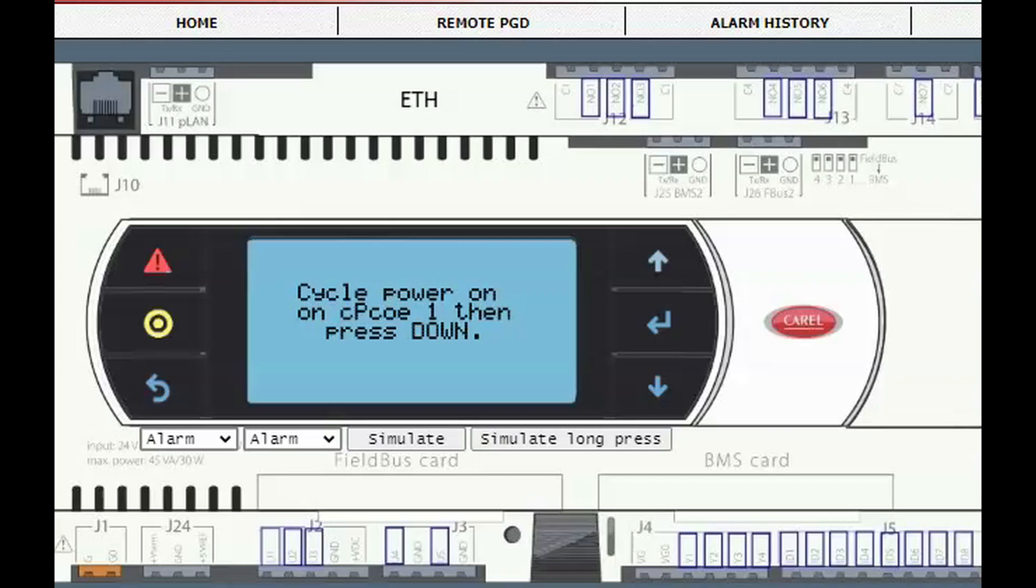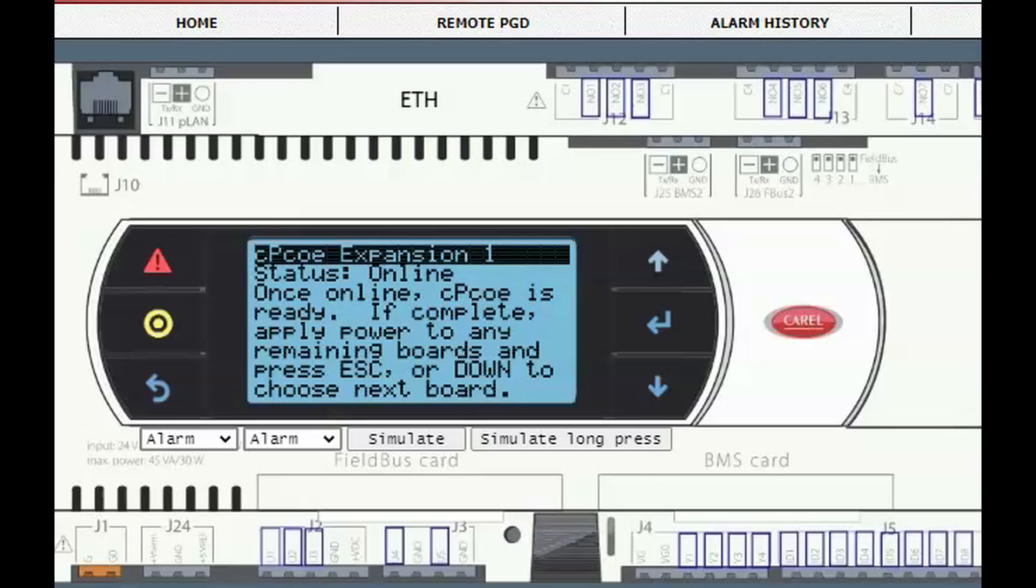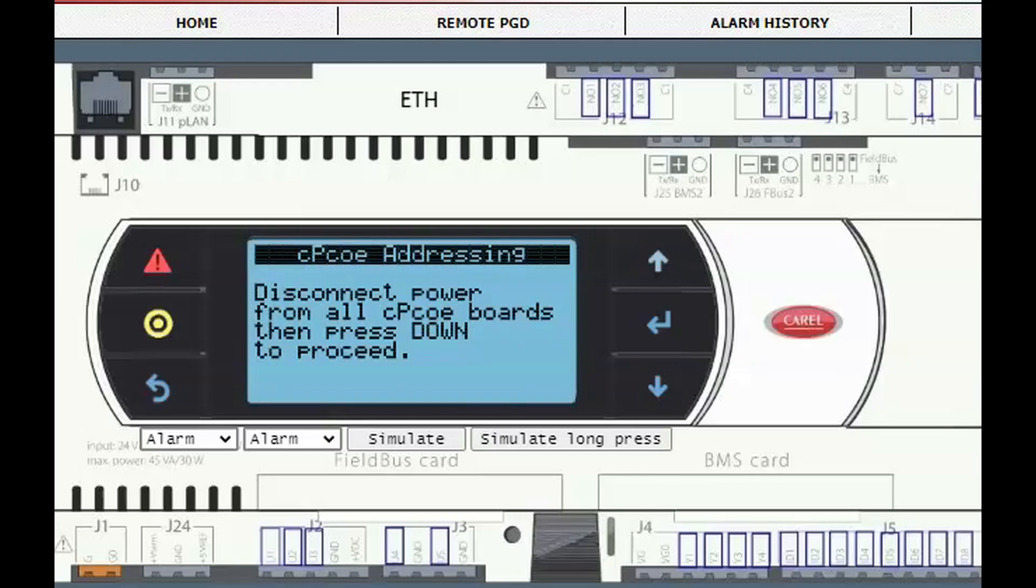When the power is restored, press down and you should see the status screen. It may take up to one minute for the status to change to online. This process can be repeated for any additional expansion boards. Note, only one expansion can be powered at a time during the wizard addressing process.